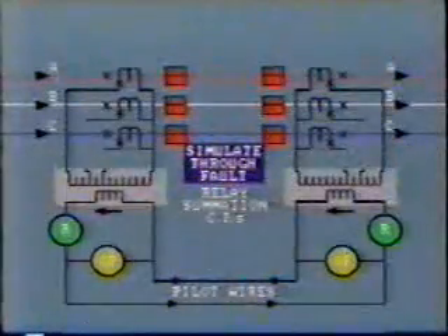We can simulate a through fault, say a ground fault on phase A, by disconnecting the CT connections to phase B and C, not forgetting to place a short across the CTs. This is usually done at the test plug board like this. With this arrangement, we should have considerable current flowing through both restraint coils and the pilot wires. Current through the operating coil should be 0 or close to 0.